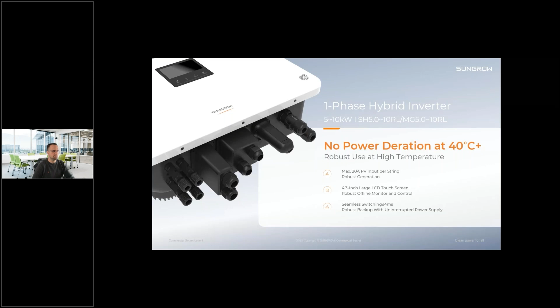The name comes from Sungrow Hybrid RL, residential low voltage, as I mentioned. This means it will be connected to our new battery, which has low voltage, connected in daisy chain to it. It has the advantage of charging and discharging the battery at 120 amps, while the battery itself handles up to 60 amps. That means two batteries can be connected to one device in parallel.